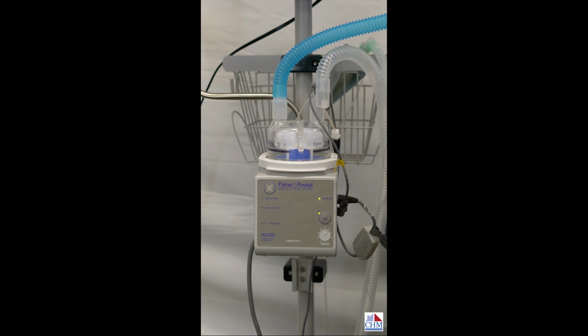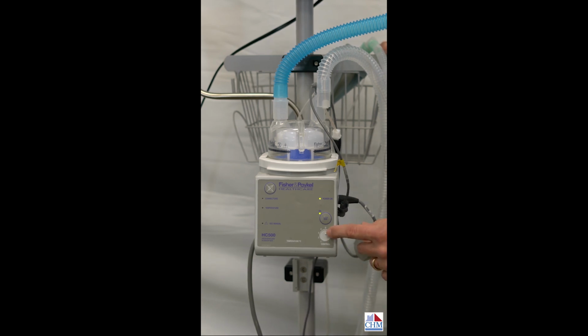The adjustment on the front of the machine for the temperature is right here. With all humidity devices, more heat means more humidity to the patient. So what we shoot for is turning this dial so that we have it set for the optimum temperature of 37 Celsius, which is body temp. So that would be the best. At times, we might turn it down a little bit for less condensation in the tubing if there's too much humidity. But otherwise, 37 is the optimum temperature that we're shooting for.